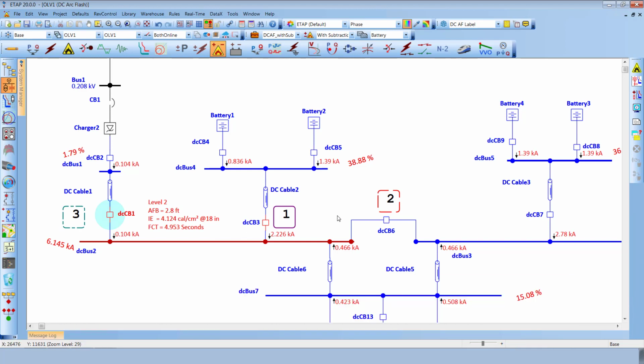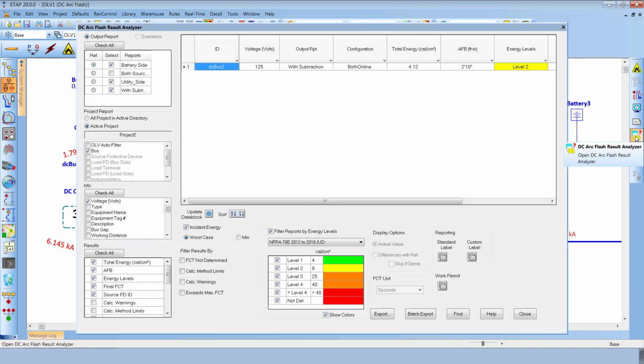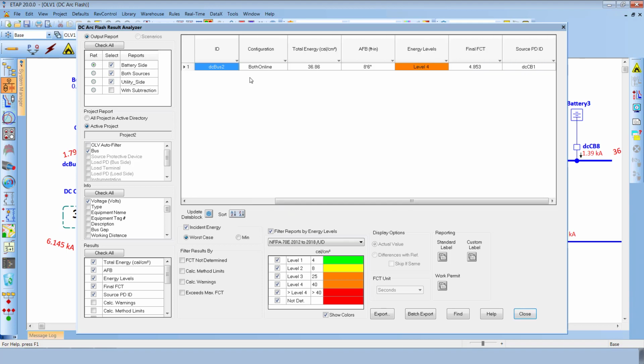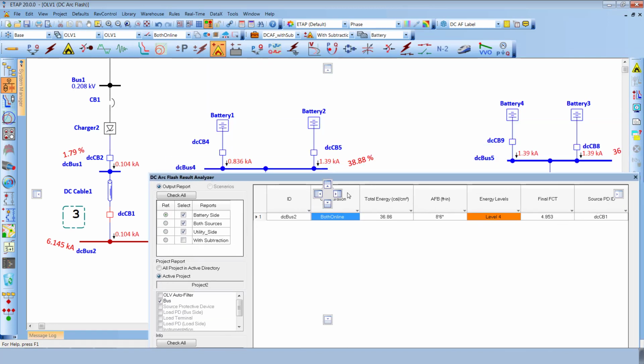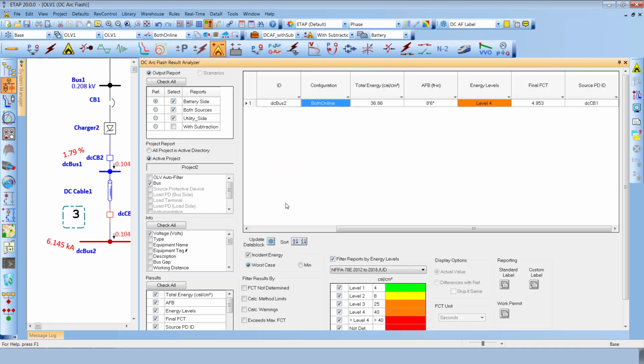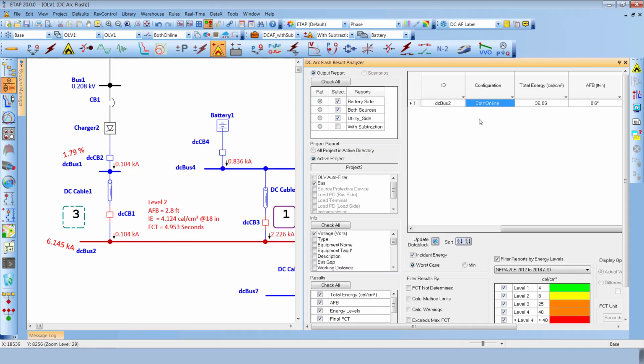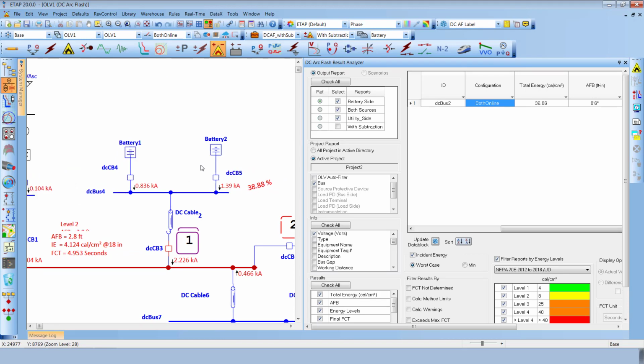Now that we explained this stage-by-stage calculation, it is time for us to analyze all the scenarios using the arc flash analyzer again. Now, as you can see in the arc flash analyzer, the original condition, the worst case incident energy, happens when there is no subtraction, which is actually in the both online configuration, where you could see the calculation of the fault current and the incident energy is calculated to be higher when both sources contribute to the fault.